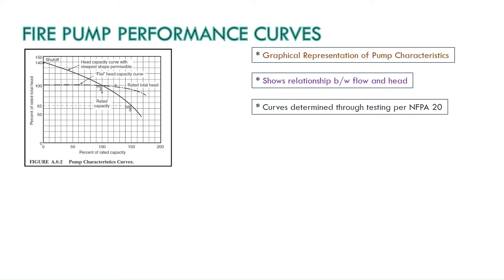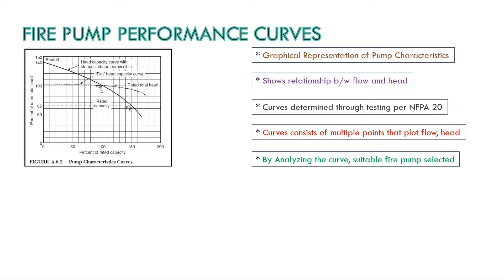This curve is determined through rigorous testing following the guidelines set by NFPA 20. A fire pump's performance curve consists of multiple points that plot the flow rate and total dynamic head at various operating conditions. By analyzing these performance curves engineers and technicians can determine the most suitable fire pump for a specific application.